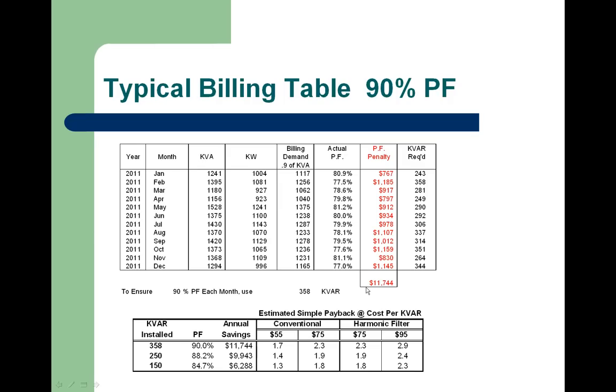So we're going to go back to the first example, which would be EnerSource, Brampton Hydro One, PowerStream, all the other utilities in Ontario other than Toronto. This is a typical billing table that we would do, where we look at the past 12 months of hydro bills to determine what the potential savings are, what the power factor is, etc. In this particular case, they say we are at less than 90%. I'm going to just try this highlighter here. We're less than 90%, so in this particular case, our power factor is 80.